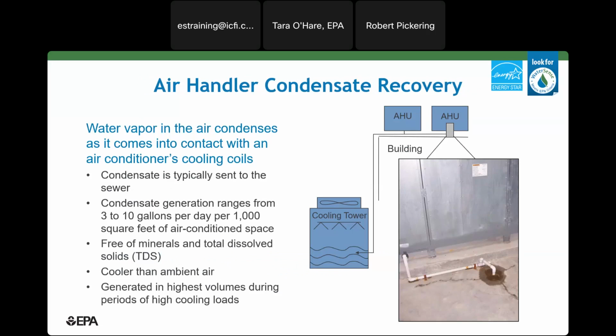In that vein, air handler condensate can be a really excellent source of makeup water for a cooling tower, particularly if the facility is located in a hot, humid climate. Condensate is water that forms on air handler cooling coils as they cool and condition outside air. The condensate is typically drained right to the sewer or a storm sewer, but since it's generated in its highest quantity when the load on your cooling tower is also at its highest, it makes an excellent source of cold, clean water.